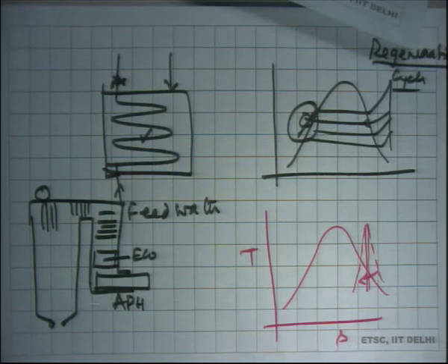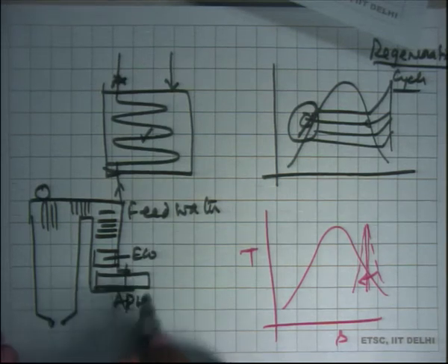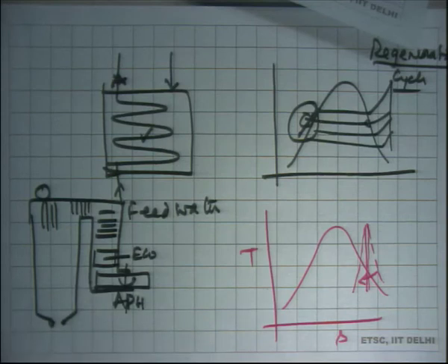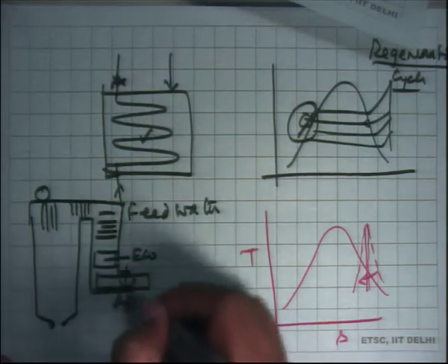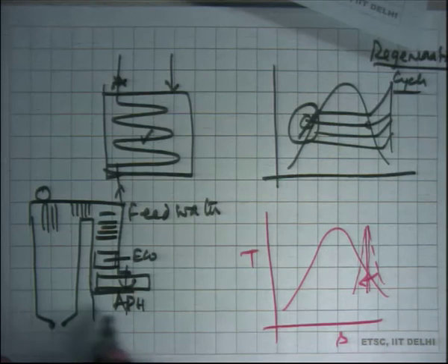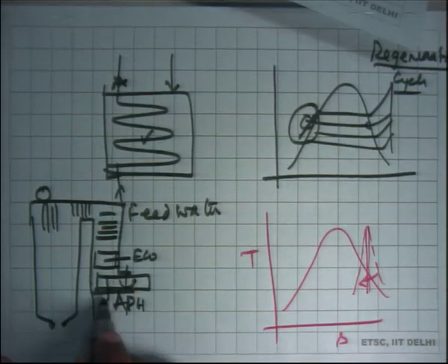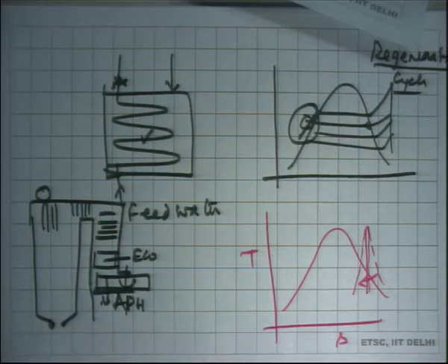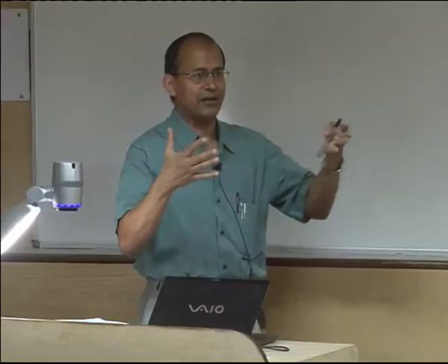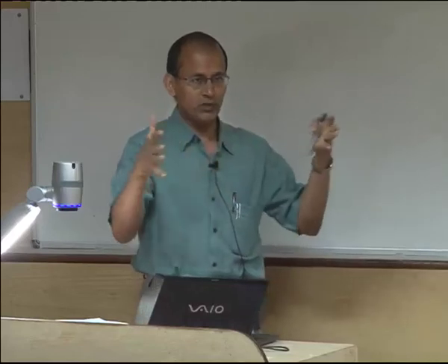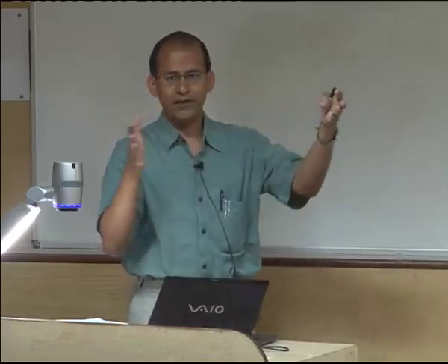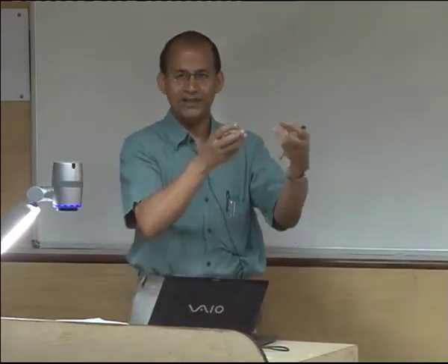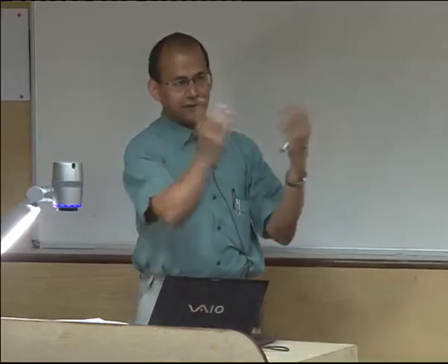Okay. So, this is a rotating wheel of a very large size. This rotates about its axis, and in rotating it goes through the hot gases and takes energy from it, and this basically rotating wheel is actually filled with scrap metal. Okay, it is a porous wheel which has scrap metal filled in it.